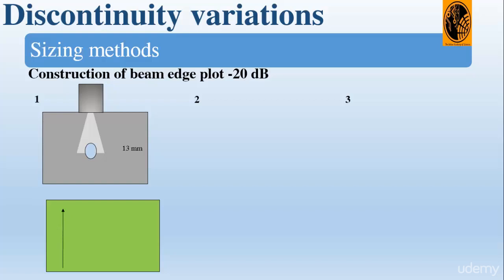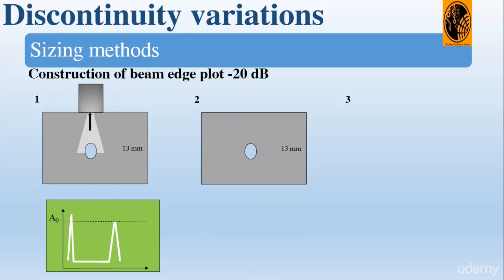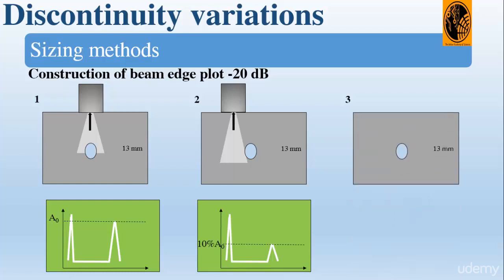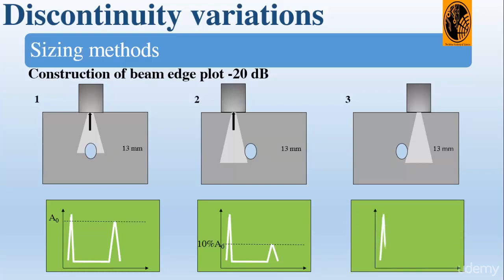Second step: move the probe to one side until the signal drops to 10% of the full screen height — 10% of full screen height corresponds to 20 dB — and mark the center of the probe on the block, as shown in the animation. Third step: move the probe to the other side of the hole until the signal drops to 10% (20 dB), and again mark the center of the probe on the block. Use the distance between these marks to plot the beam on graph paper.